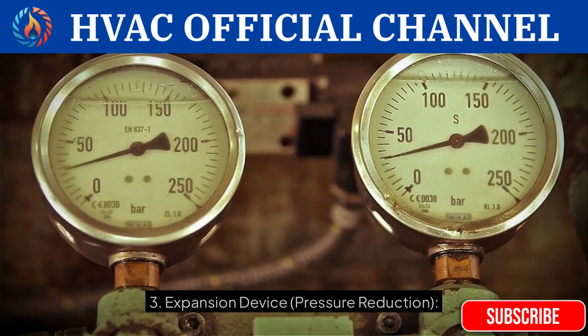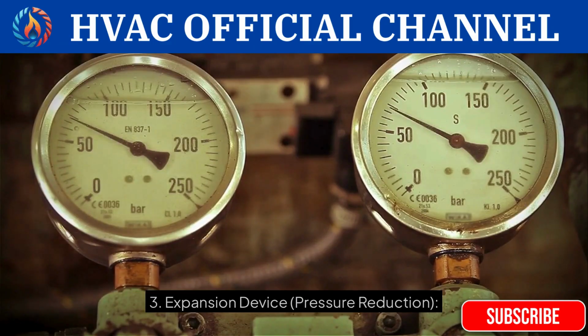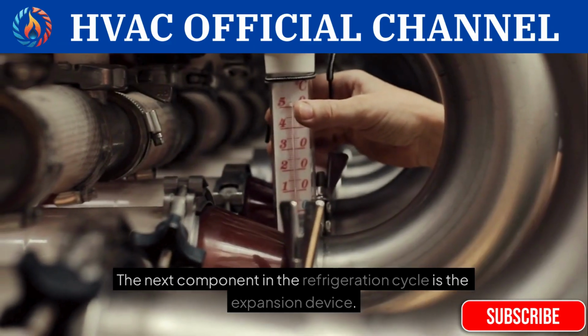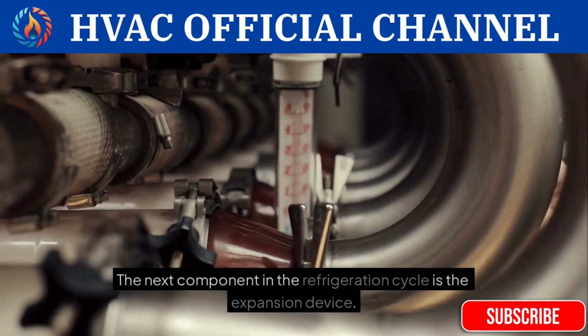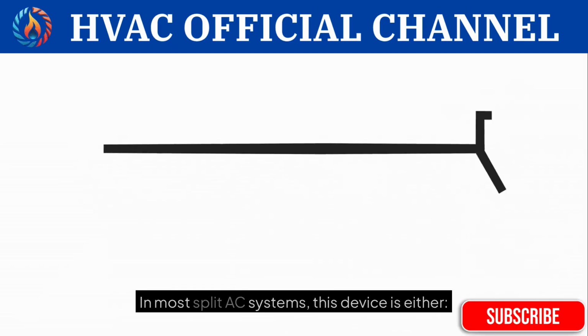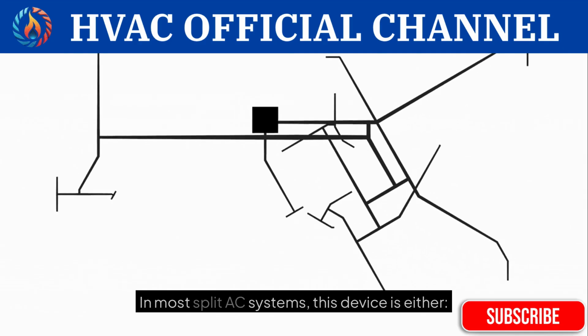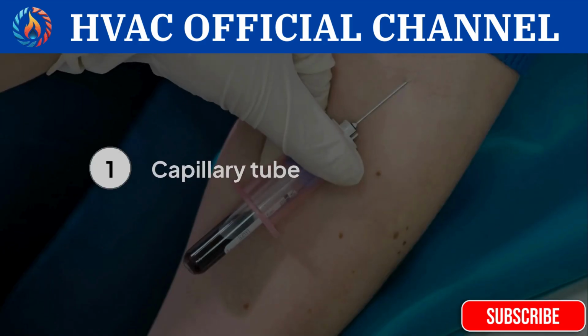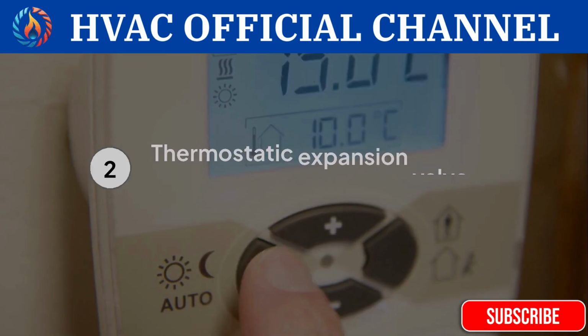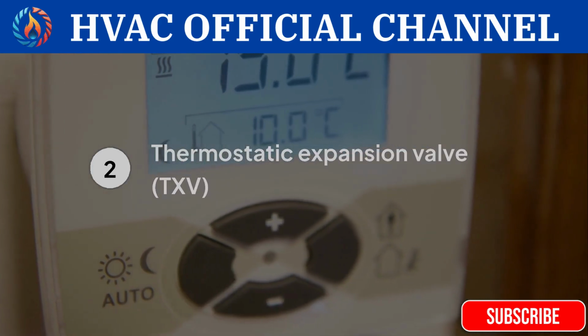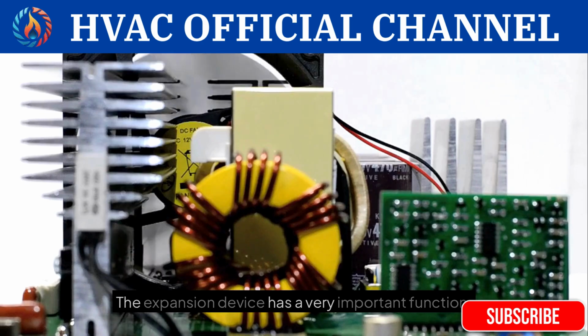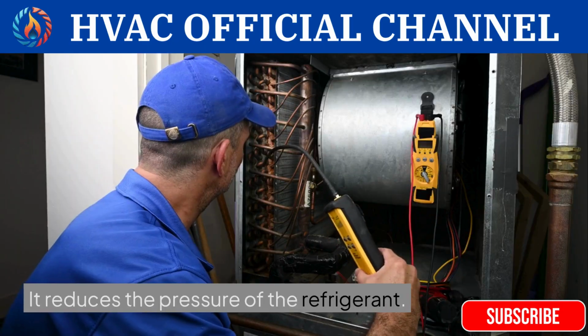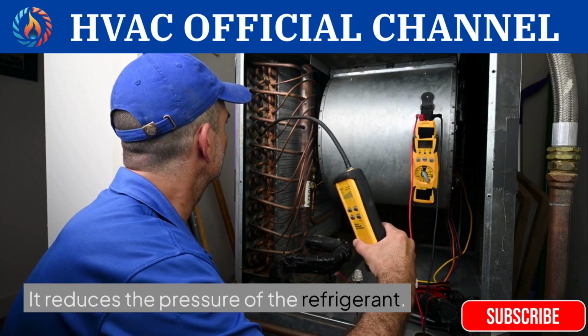3. Expansion device, pressure reduction. The next component in the refrigeration cycle is the expansion device. In most split AC systems, this device is either a capillary tube or a thermostatic expansion valve, TXV. The expansion device has a very important function. It reduces the pressure of the refrigerant.